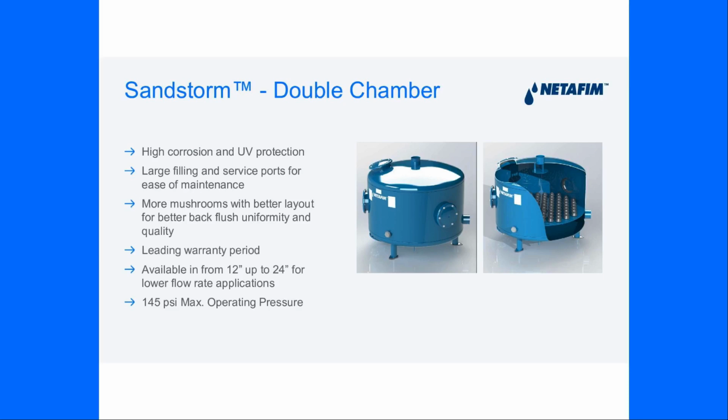In addition to that, if we needed pressures in excess of 115 PSI, then we could go to a double chamber, where we can go up to 145 PSI maximum operating. And some of the same characteristics of single chamber, for example, the high corrosion and UV protection, are equaled here in double chamber, as well as the port sizes, et cetera. So that's Sandstorm double chamber.